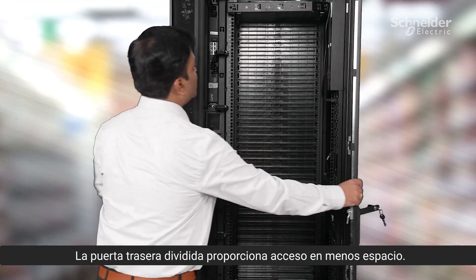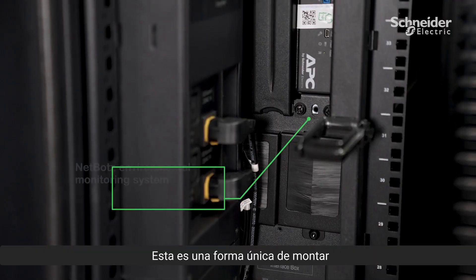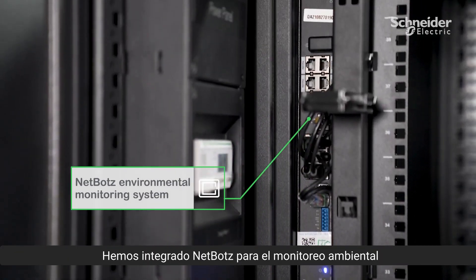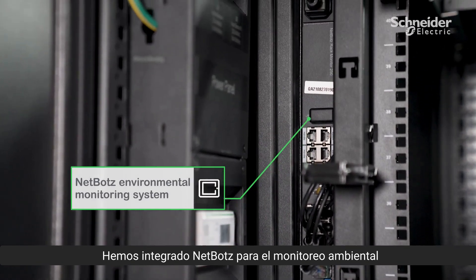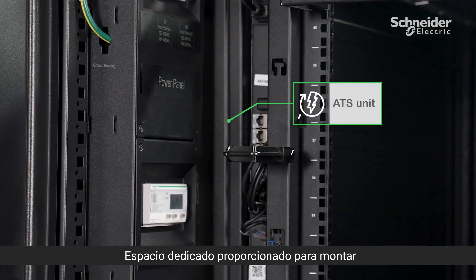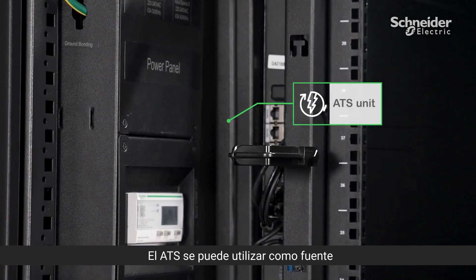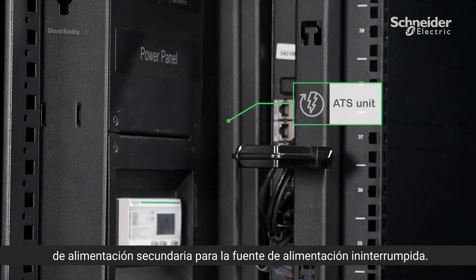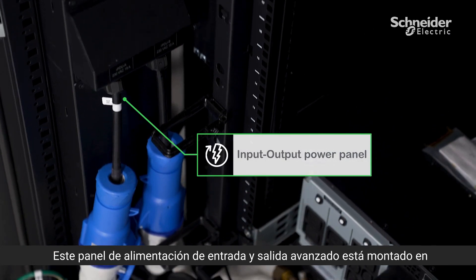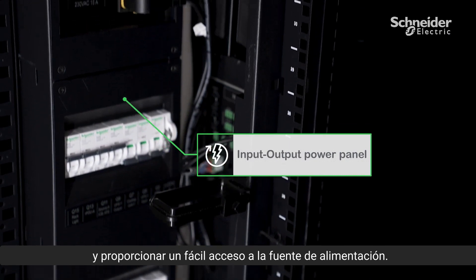The split rear door provides access in less space. This is the unique way to mount NetBotz and ATS in zero-U space. We have integrated NetBotz for environmental monitoring which connect different sets of sensors. Dedicated space is provided for mounting the optional ATS unit, which can be used as a secondary power source for uninterruptible power supply. This advanced input/output power panel is mounted in zero-U to save IT usable space and provide easy accessibility to the power source.